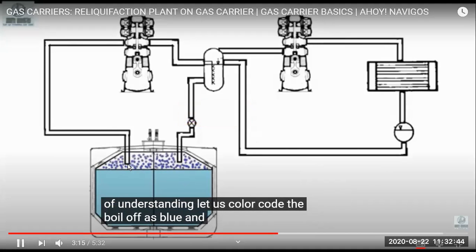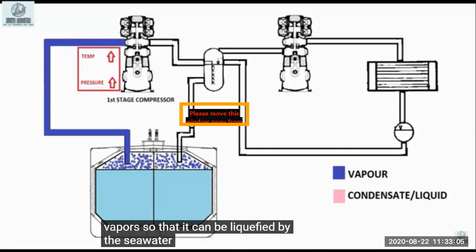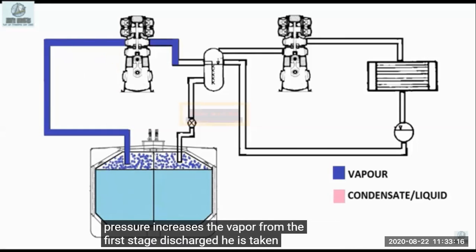The gas is boiling off from the tank. The boil-off is taken from the tank and goes to the compressor. The compressor, by external work, raises the pressure of the cargo vapors and the gas gets heated — so temperature increases and pressure increases. It will start moving toward liquid state, though some vapors will still remain. That's why we have a two-stage compressor, because the first stage alone cannot convert all the gas to liquid. The intercooler then cools down the gas and increases the efficiency of the plant.